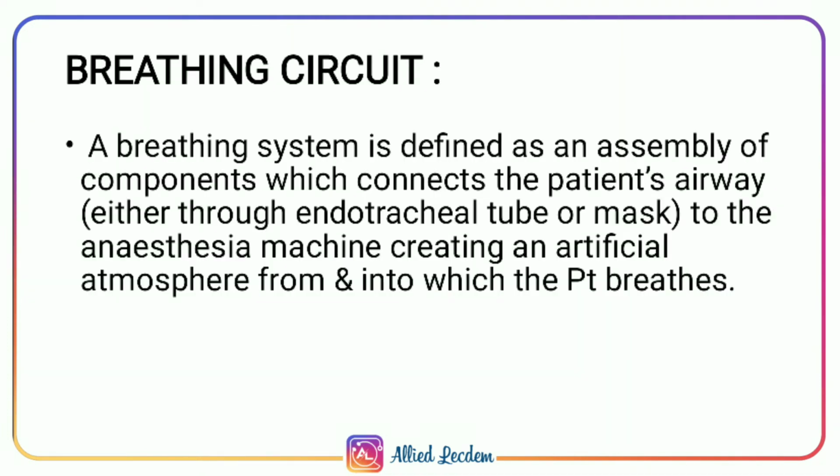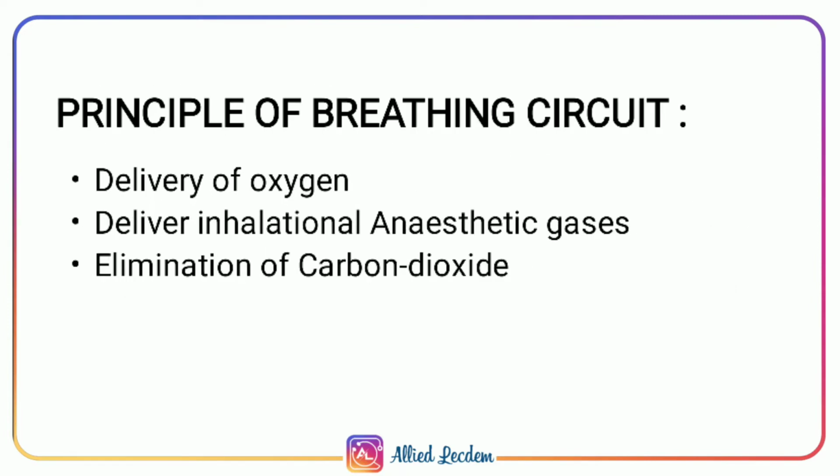A breathing circuit is a medical device which is used to deliver oxygen or any inhalational agent like sevoflurane, desflurane from the machine to the patient via an endotracheal tube or a mask. This is the main source of respiration for patient during any surgical procedure. Principle of breathing circuit: delivery of oxygen, delivery of inhalational anesthetic gas, elimination of carbon dioxide.